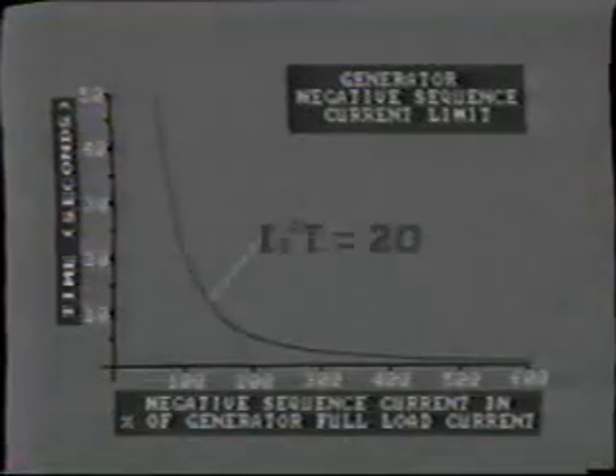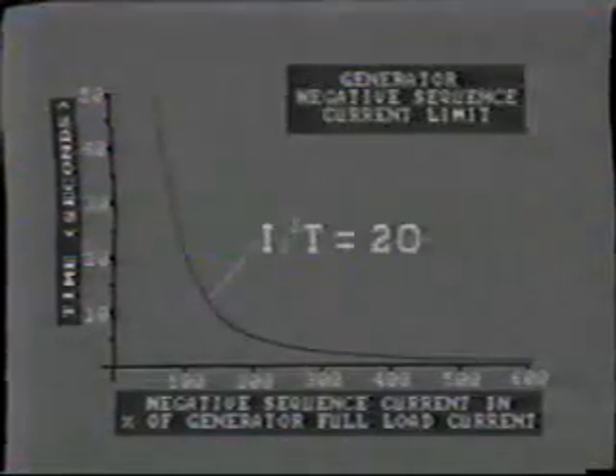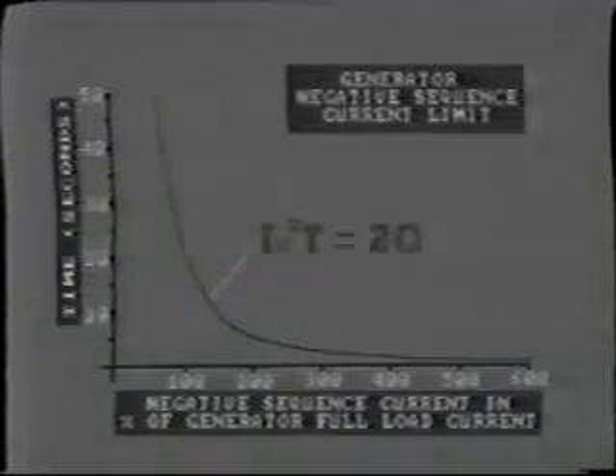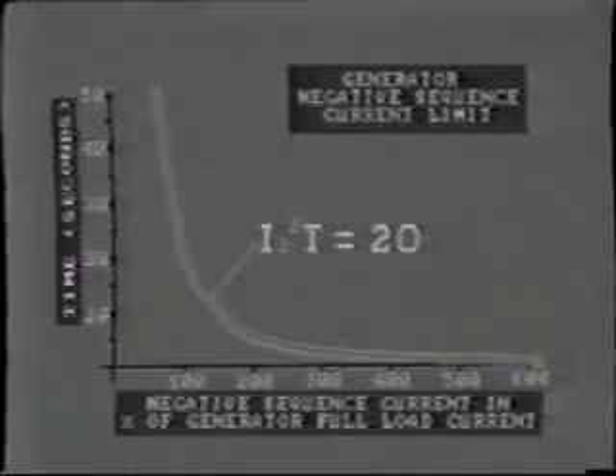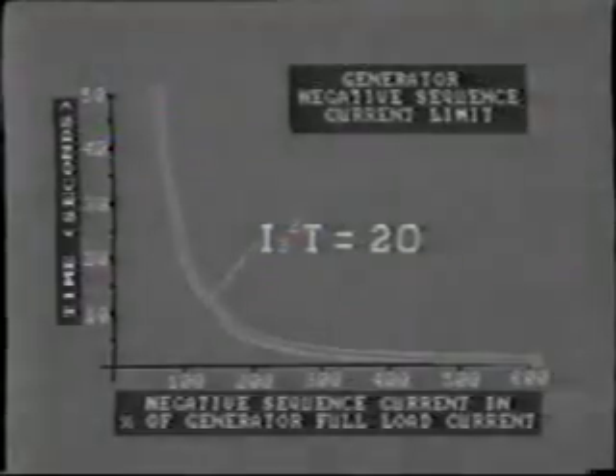This limit is, in fact, a combination of current and time. It is proportional to the square of I2, that is, the negative sequence current, times T in seconds. A lower negative sequence current can be tolerated for a much longer time period. The negative sequence relay measures this combination of current and time and is set to alarm or trip the unit to prevent damage.